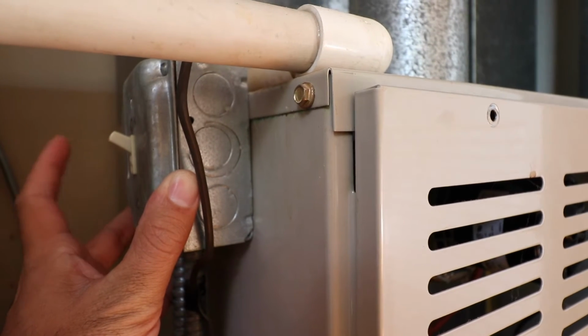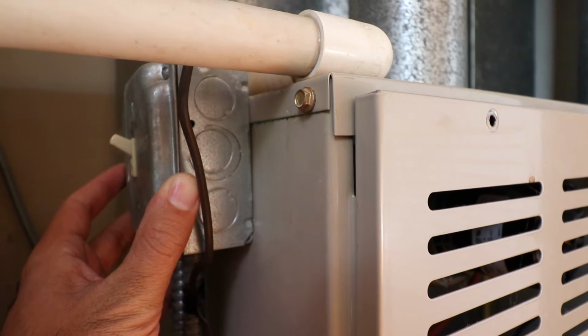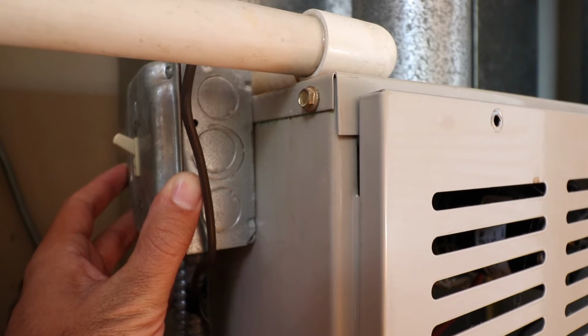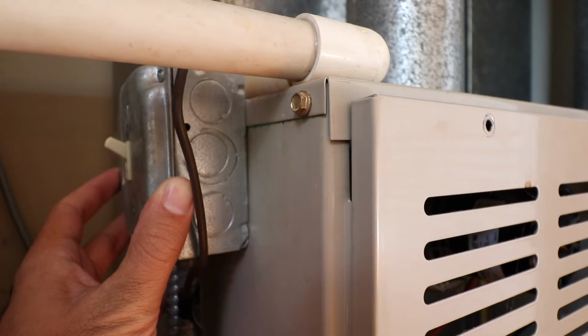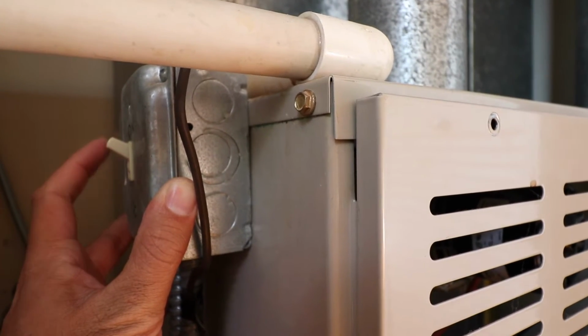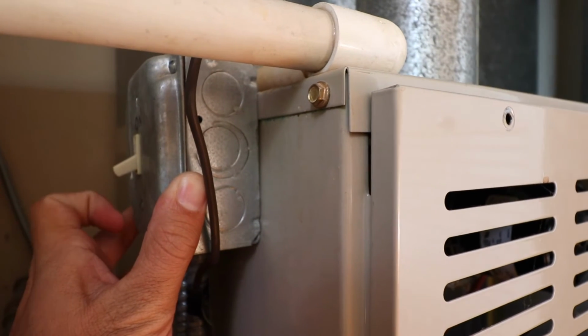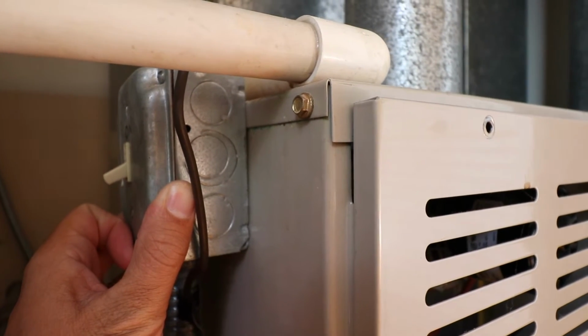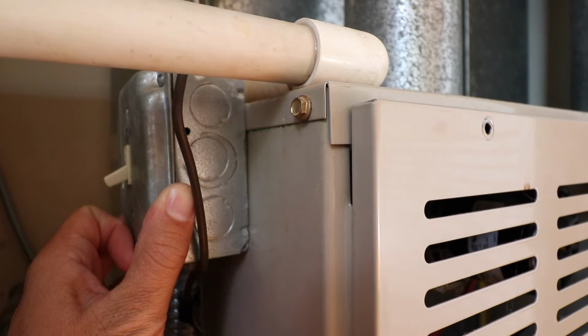Sometimes the power shut off is a light switch in the same room as the HVAC system or in your mechanical room. What I like to do is make sure your unit is running so you can hear it, and then when you flick the switch off, you'll hear the unit go off, confirming you've cut the power.